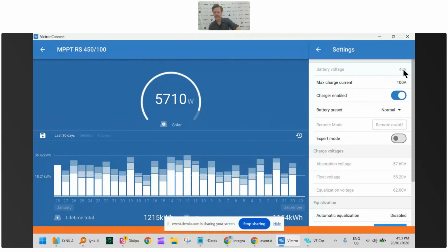What's quite important with Victron MPPTs is that, and you can't change it on here, but if you're using something like the 250-100, you should set the battery voltage before you apply any PV. So when you first fire up and you've wired up your system, when you want to first engage with the MPPT and put power to it, don't turn on the PV - turn on the battery first. Then it's going to detect that it's a 48-volt system, and also boot up and allow you to log into it and make these changes in the settings.